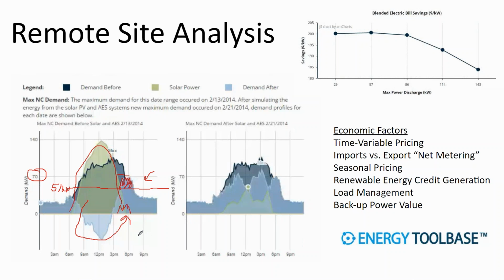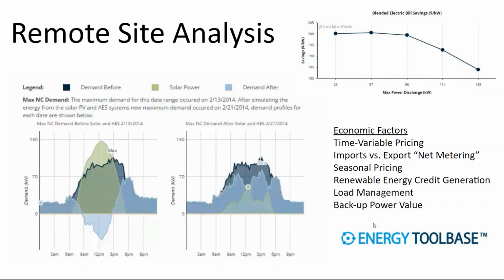And that's, on a sunny day, very easy to do. On a partly cloudy day, that's still pretty easy to do. But on a partly cloudy day, we're running our battery more, our solar array is doing less. And then, of course, on a completely overcast day, maybe my building load is down, but I'm still running my battery. I have to make sure I have enough power from the previous day or two's worth of solar to go in and charge that battery fully. And so eventually the model gets so complicated that you really need to use a computer and more than just a basic spreadsheet to figure it out.